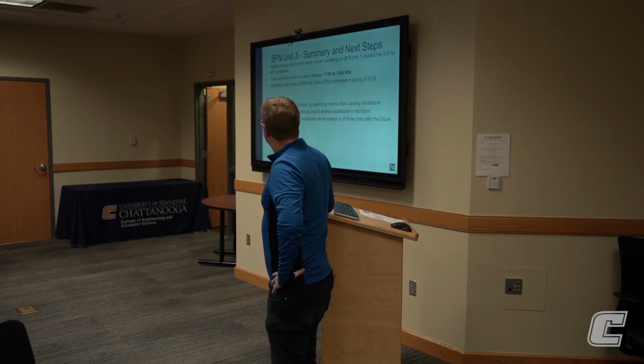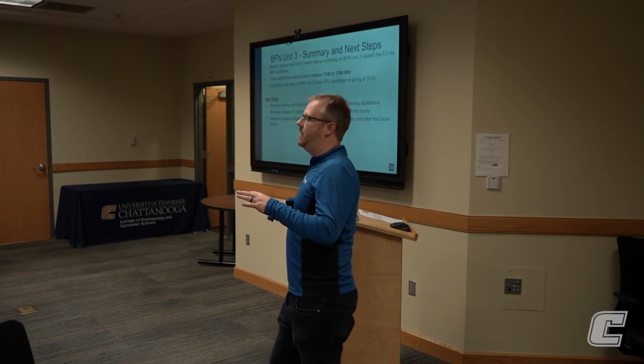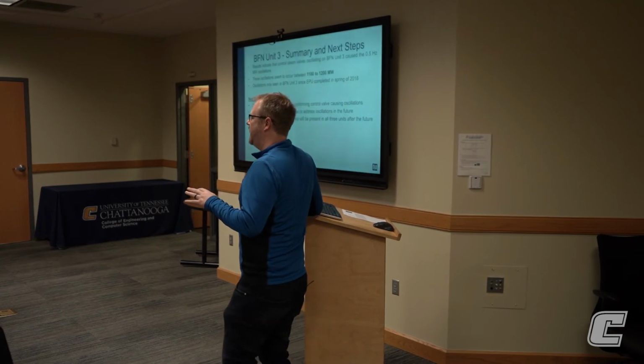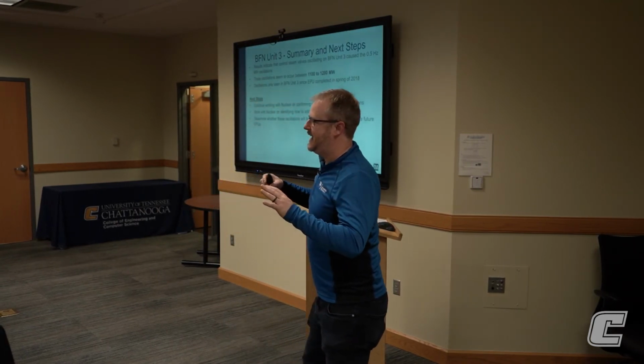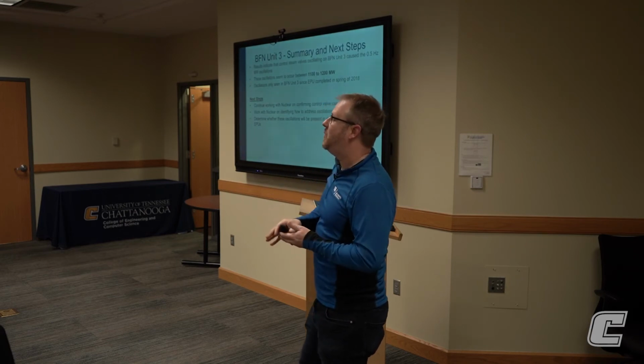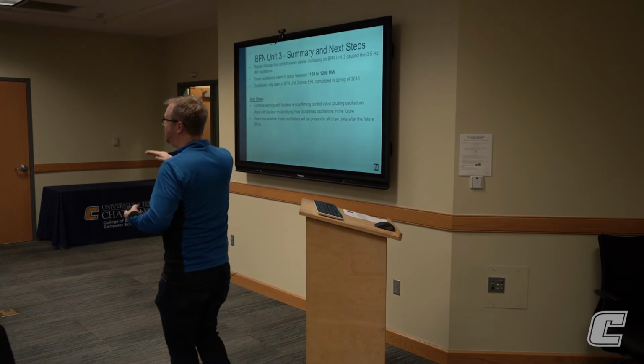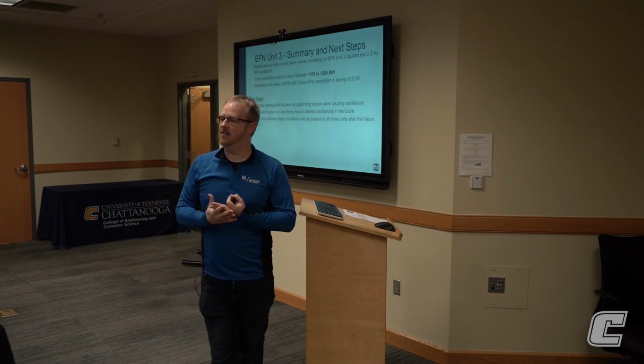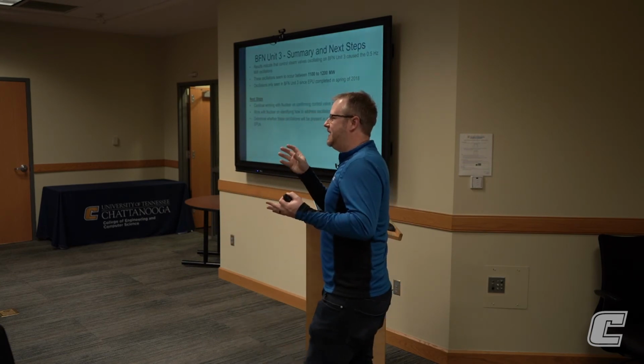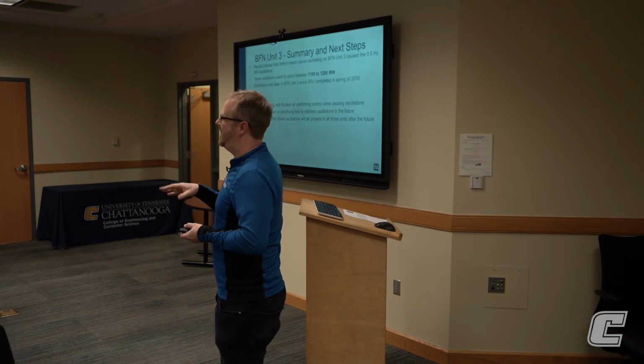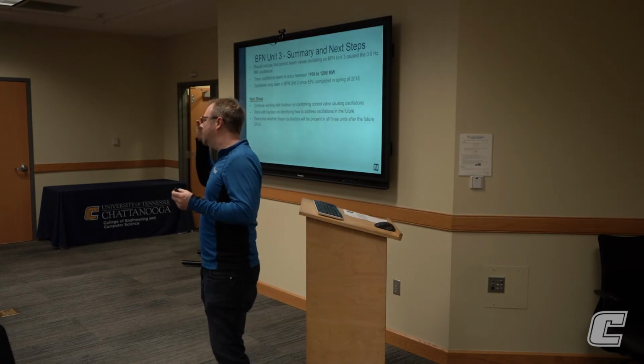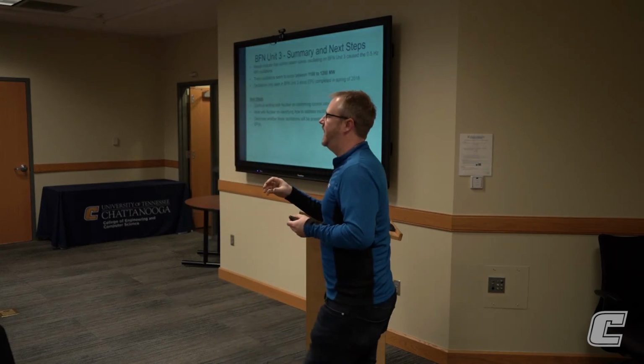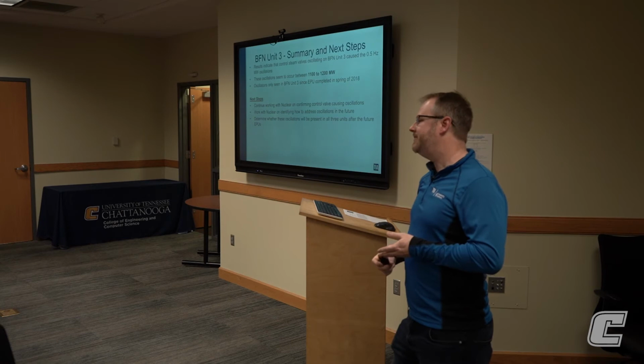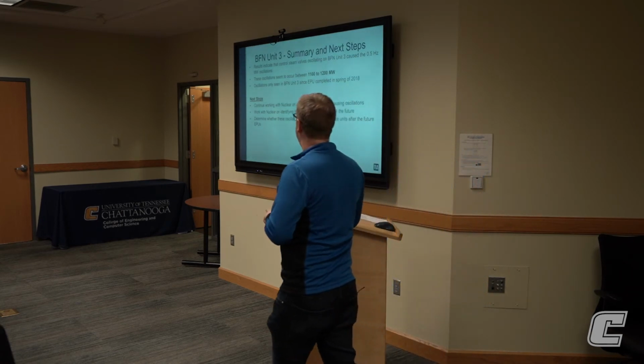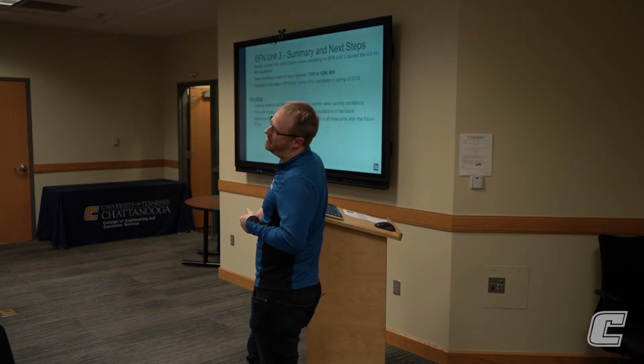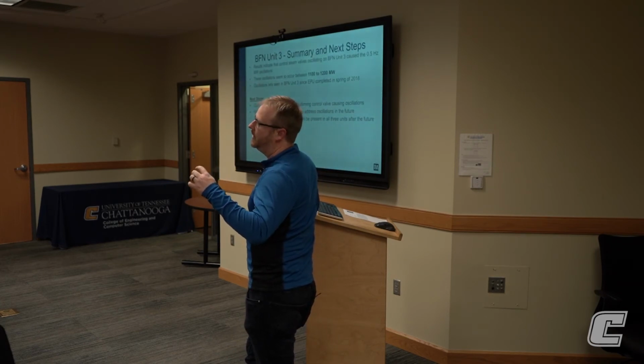And it turns out to be a steam valve. There was a steam valve that was just fluttering. It wasn't seated properly. It didn't know if it should open or close. It was in this unknown area. And that's why when they increased steam pressure to get more output of the unit as it was going up, it would seat properly and the oscillation would go away. But in this no man's land, and this was a setting issue. This was not a faulty valve, but it was the wrong setting. The steam valve was just fluttering and it was causing the unit to oscillate. So that's what happened here. They went in and fixed the setting for the steam valve, narrowed its margin on the controller, and that fixed it.